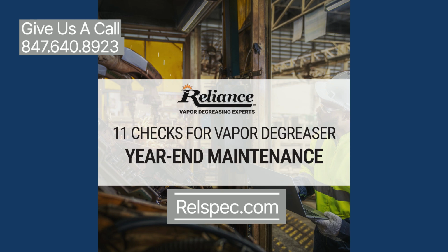Check 3. Conduct an external inspection of the vapor degreaser. Walk around the vapor degreaser and observe the condition of the system. Check for signs of leaks, in particular on piping, ball valves, clean out access doors, filtration canisters, pump housings, spray reserve tank, water separator, and water separator lid gasket. Next, check for any damage to any component that might require repair or replacement.